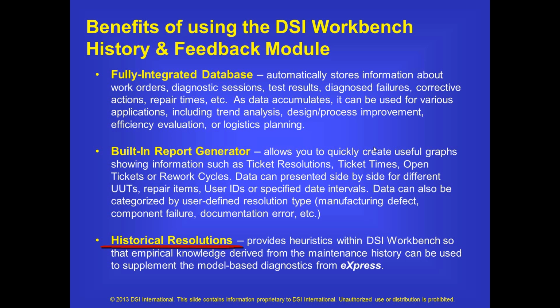And then finally, the third major benefit is what we're referring to as historical resolutions. Whenever you finish a job within a diagnostic session in DSI Workbench, you enter what actually was the cause of the issue. It may be the replacements you did, or that there was some improper documentation, or test equipment wasn't being hooked up correctly, etc. It stores them within the database, and then these can be used to extend the diagnostics possibilities within Workbench.